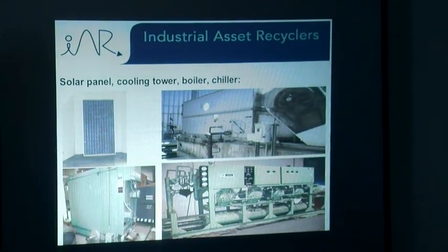This is what they call a water-to-water chiller. It takes water in from an input circuit through a cooling tower, which cools the water by dropping it over material with a fan on the exterior. Then there's refrigeration - in this case 4 reciprocating compressors, like in a refrigerator. A heat exchanger at the bottom takes that chilled internal water and re-chills external water that can go to air handling units to cool buildings, or even be used in ice skating rinks to drop the temperature way down.